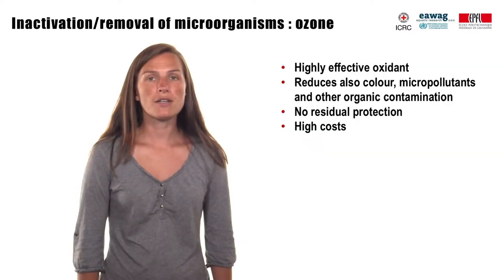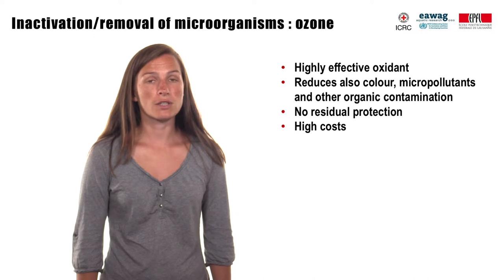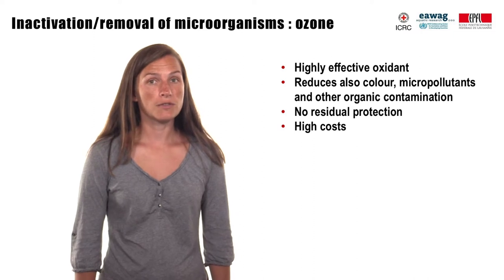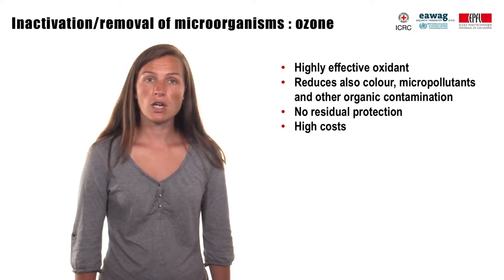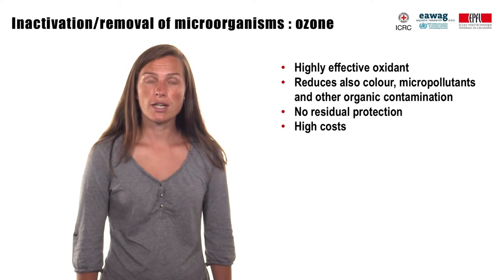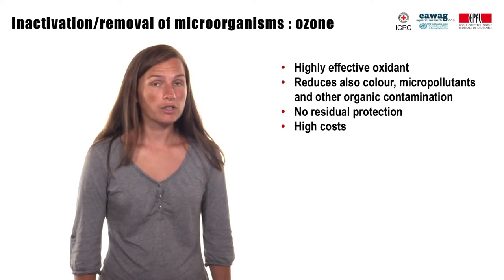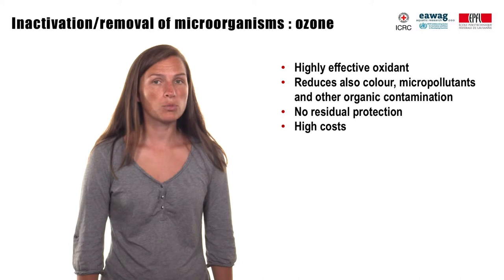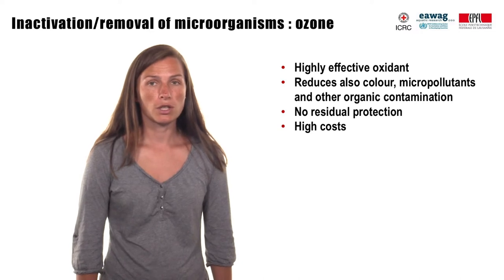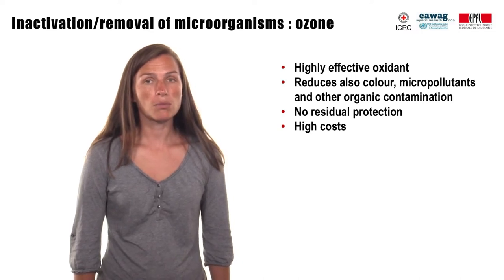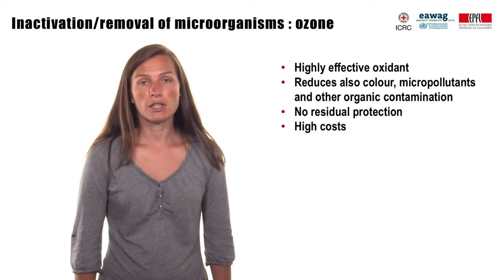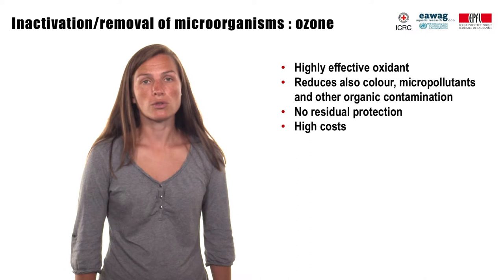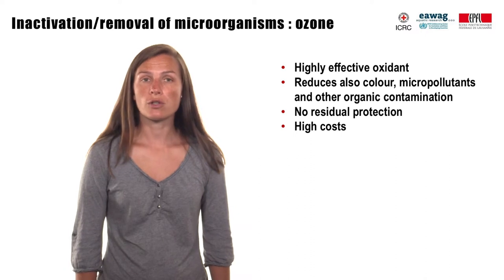Ozone is a highly effective oxidant, not only disinfecting water but also reducing color, micropollutant content and other organic contamination. It is however expensive and does not provide residual protection. Due to high cost and relative complexity, it is usually not used in an emergency context.